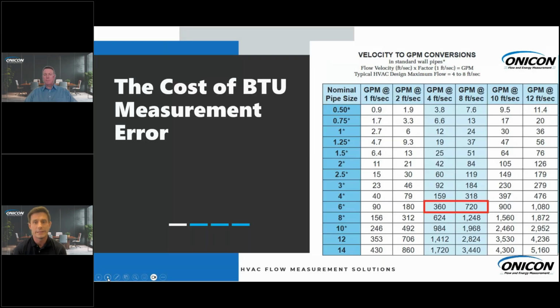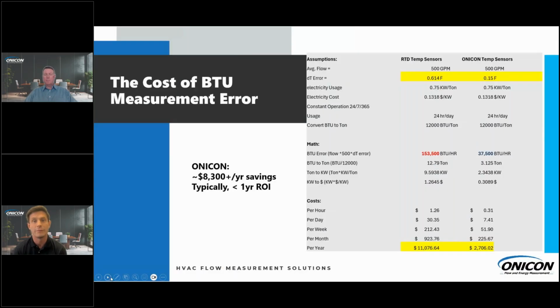So let's look at an example. Let's assume that we have a 6-inch pipe. As you can see, we have a wide range of flow, 360 GPM up to 720. Let's assume that we're using an average of 500 GPM in the 6-inch pipe across the day. You can see the difference here in the table between the RTD temperature sensors versus the ONICON temperature sensors. That delta T error, the first thing in yellow there, is 0.614 compared to our 0.15. And then you see the electricity usage, that chiller that we mentioned earlier, 0.75.